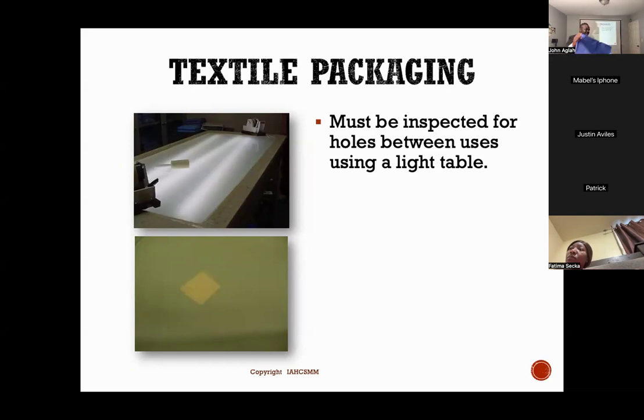So you have your blue wrap like this. And the blue wrap comes in different sizes. So if you are wrapping something that is small, you may have 18 by 18, something like this, right? 18 by 18, you have 20 by 20, 24 by 24, 30 by 30, 35 by 35, or 34 by 34, 40 by 40 size. So as the size goes up, it becomes bigger because there are certain trays that are that big. So if you do not have a big wrap, you cannot wrap it properly.